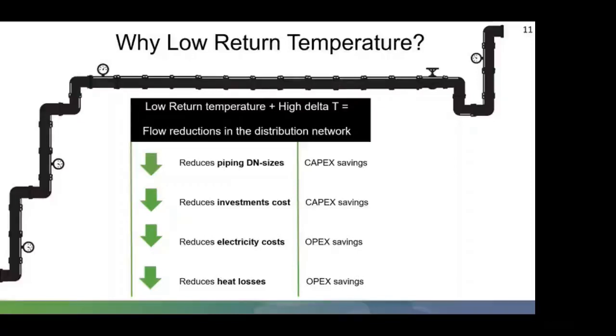So if you look at the slide in front of us, reduced pipe sizing, capex saving. Again, that benefits you when you're designing a building. Reduced investment cost, again, capex saving. You're looking at smaller pumps, smaller controls, cheaper insulation. Reduced electricity because you're going for smaller pumps, smaller control valves, opex saving. So I have conversations with housing associations on a regular basis, and it's not so much the capex saving they're looking at, it's the 25 years of operational cost that potentially saves them a lot of money. Reduces heat loss, again, because you've got smaller pipework, better insulation. Again, it's an operational saving. So over the lifetime of the building, the energy cost is significantly lower.